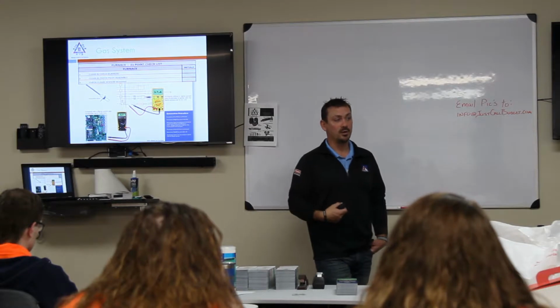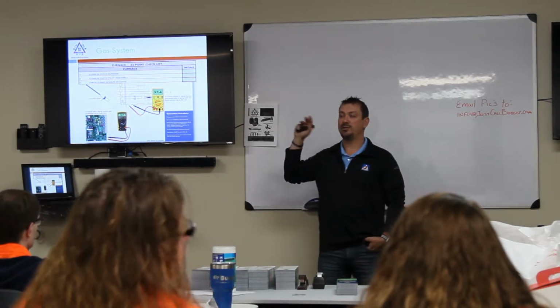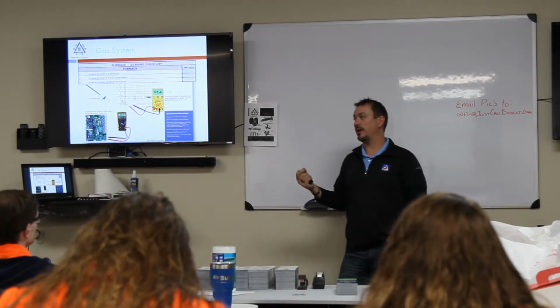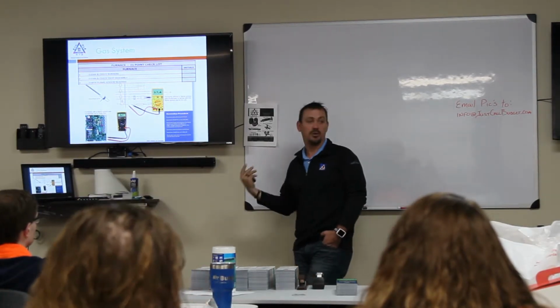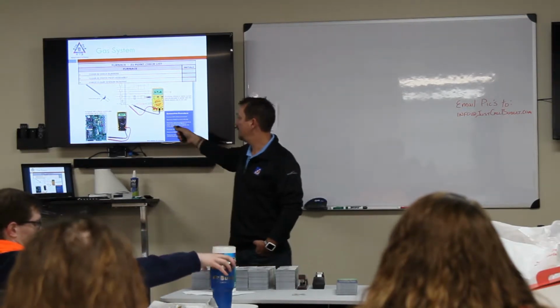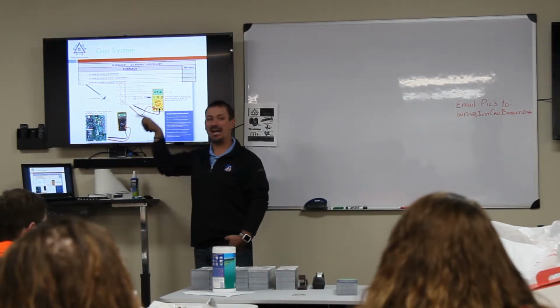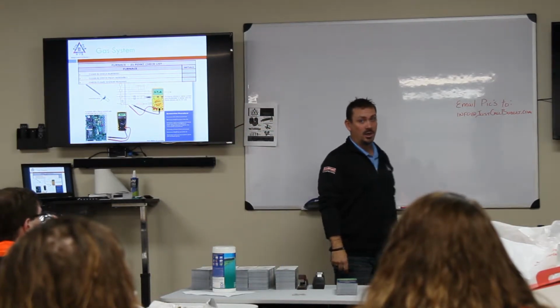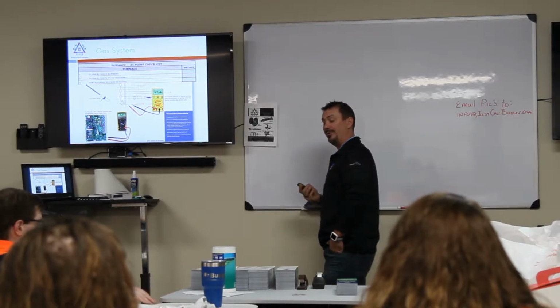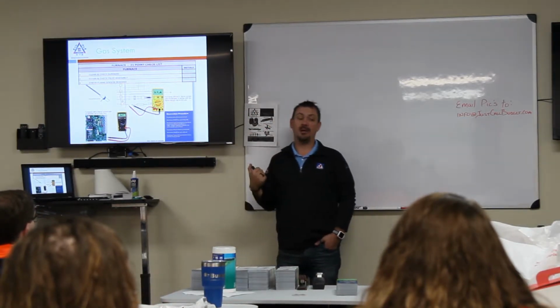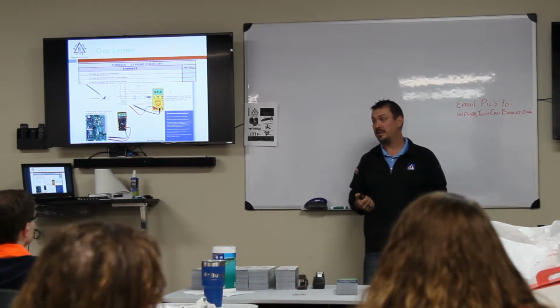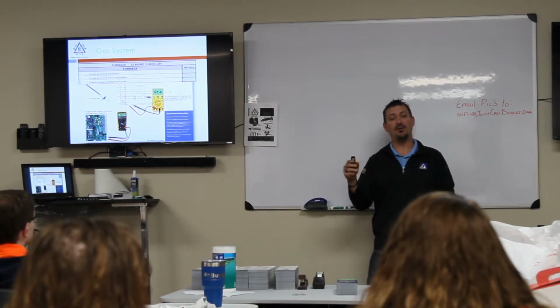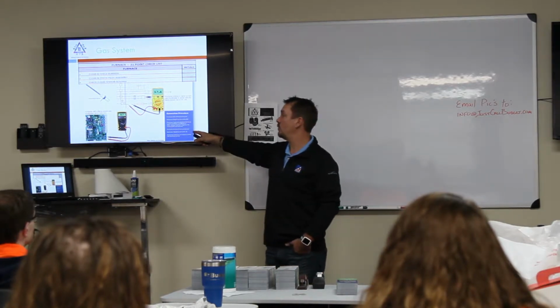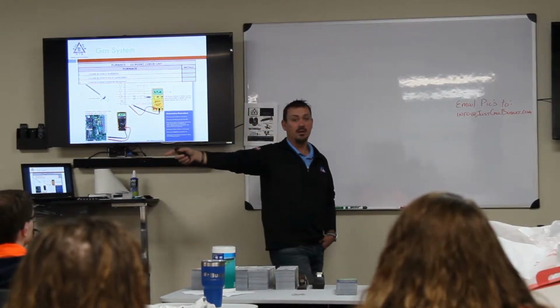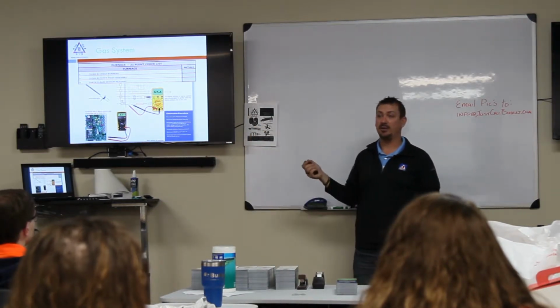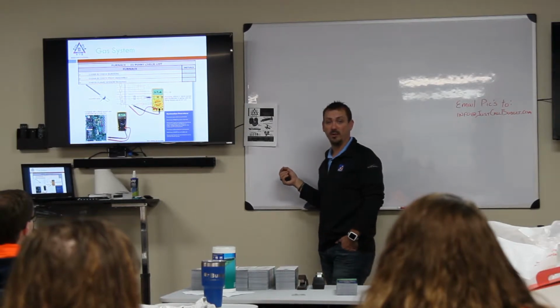And how that flame sensor works is the control board is sending voltage out through the flame sensor. It does not work like a thermocouple where the flame hits it, heats it up, and the signal gets sent back through the wire from that flame sensor. That's not how it happens. There is voltage that's being sent out from that wire, and every board will do it a little different. Some boards do 120 volts, some do about 80 volts. It just depends, and that is AC. And then when the flame hits it, it rectifies it and goes to volts DC, and that's where the volts DC comes into play.